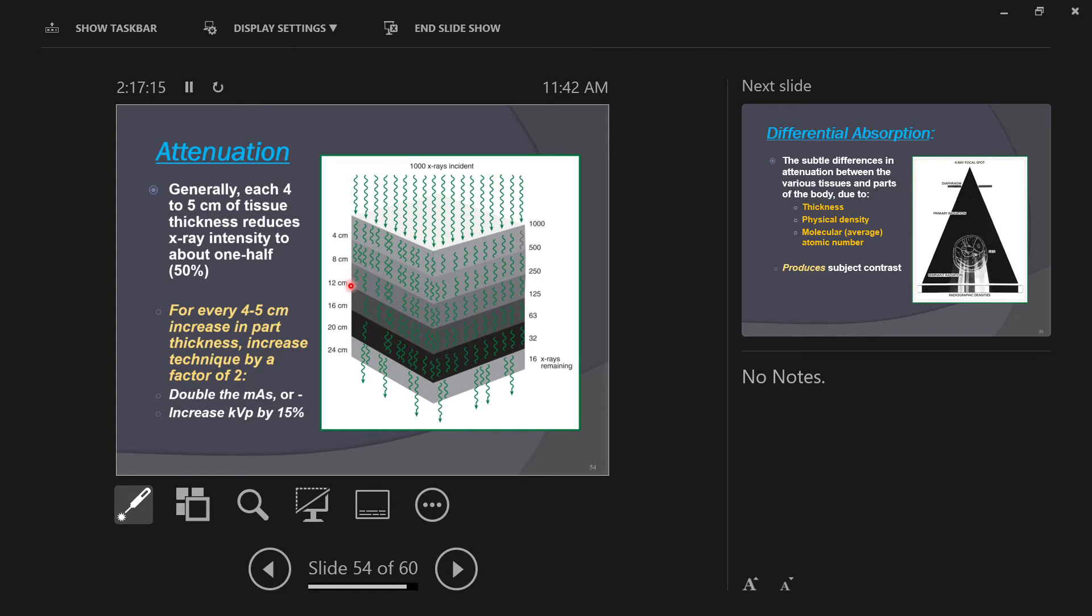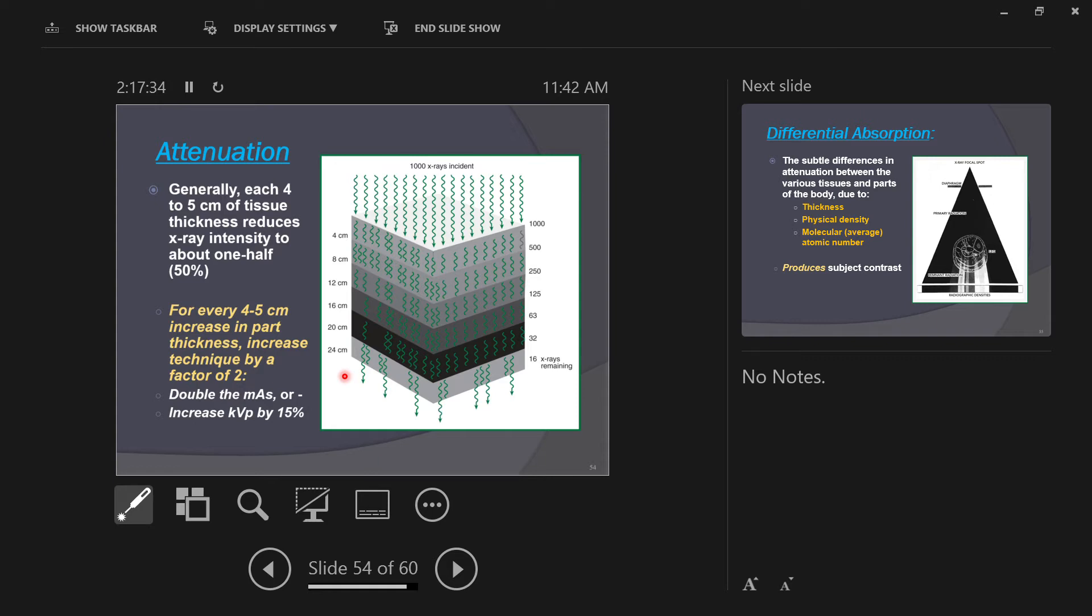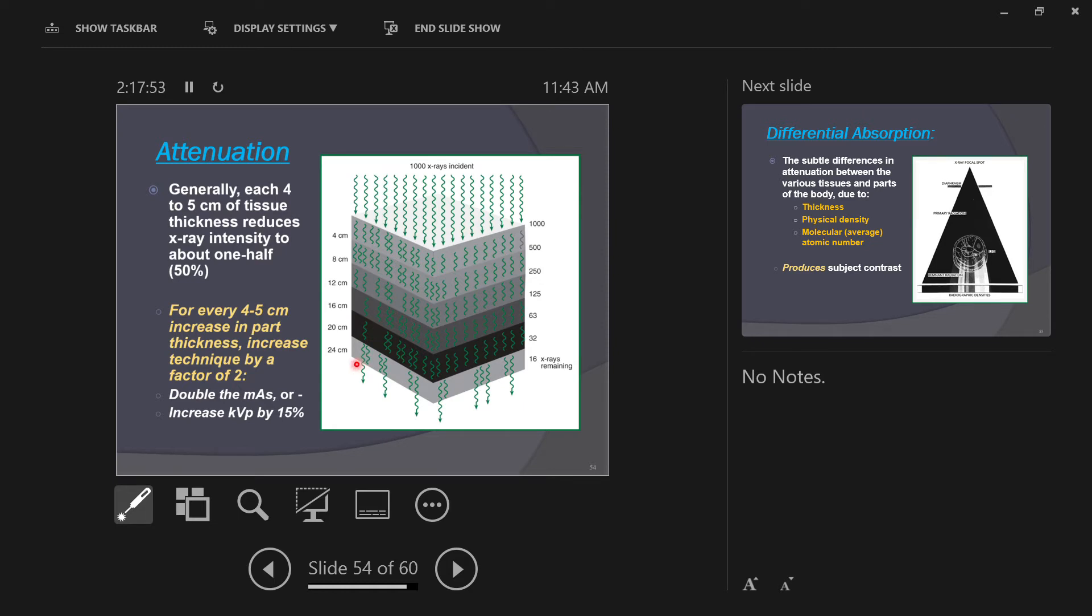Passing out of the eight centimeter depth, you have 250 x-rays left over. You get the story here: 8 to 12 centimeters, 250 to 125; 12 to 16 centimeters, 125 to 63; 16 to 20 centimeters down to 32. We're cutting in half every four centimeters of tissue depth. At the last depth of 24 centimeters, which is about the depth of an average adult's chest, you have 16 x-rays remaining. That's only 16 x-rays because we started off with a thousand. So you have to use this to calculate how much MAS or KV you need to set on your equipment.